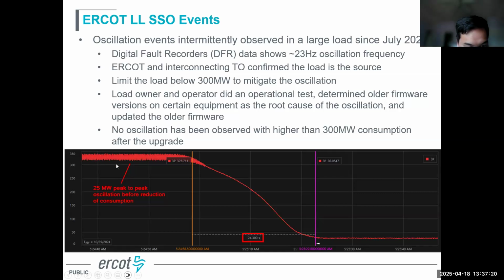So you can see from here, we have oscillation of 25 peak to peak when the consumption is between 300 and 350. And if we reduce the consumption of the load, the oscillation goes away. So we engaged with the load owner and operator, and they did an operational test. They determined that it's a firmware issue. They said some older firmware version on certain equipment is the root cause of the oscillation. Then they updated the older firmware. After that, even when the consumption is above 300 megawatt, we have not observed any oscillation.